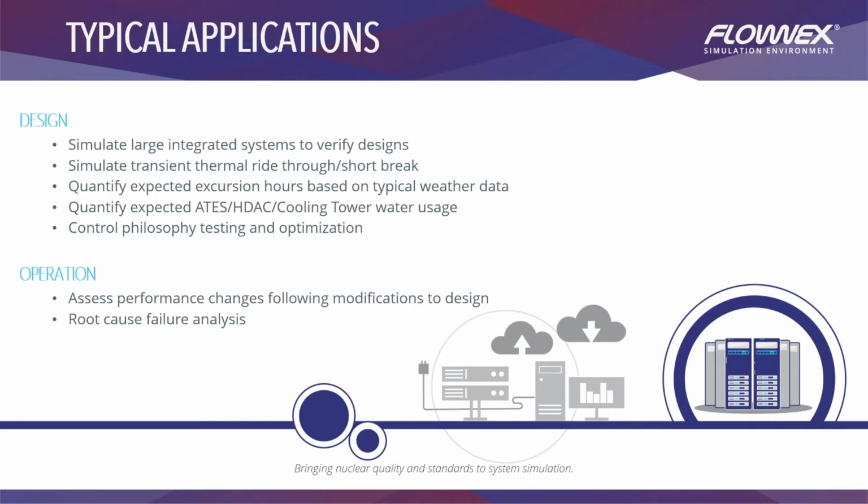The common applications here are water usage when using heat exchangers such as hybrid dry coolers. These are often Adiabatic heat exchangers, for example. And when data centers are deployed in cities with limited water available, it's often required to quantify that water usage for the correct application of permits. So Flownex is particularly useful in taking weather data and being able to use that to quantify the amount of water used in different environments.